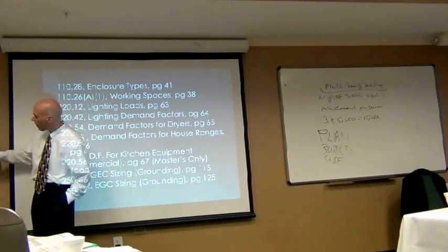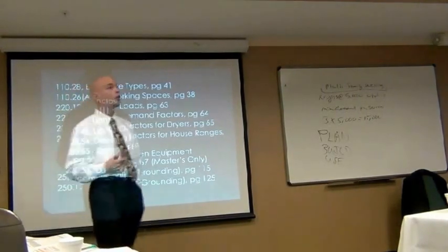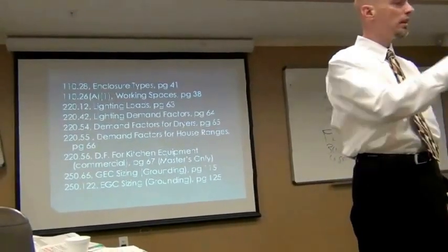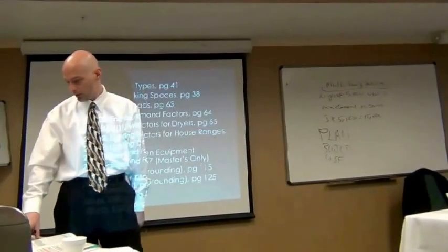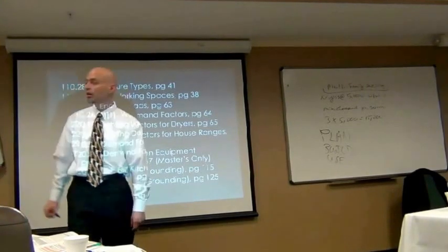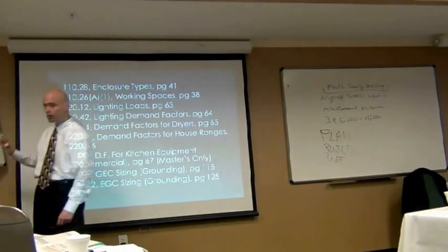You would take the sum of all 3 of these ungrounded conductors here, which is 250, 250, and 250, a total of what? 750 kc mil. The lump of that would then be applied to the table. So you basically size it based on a 750 kc mil, which would put you at the second to the last bottom, and that would be a 2-aught copper conductor. So each one of these sets would then require a 2-aught copper GEC.